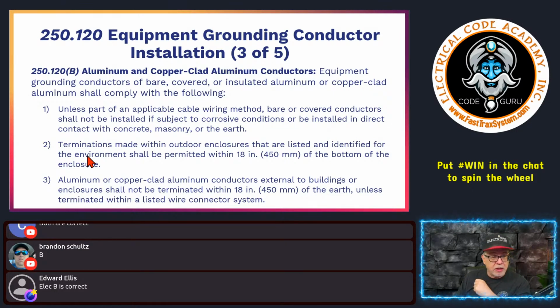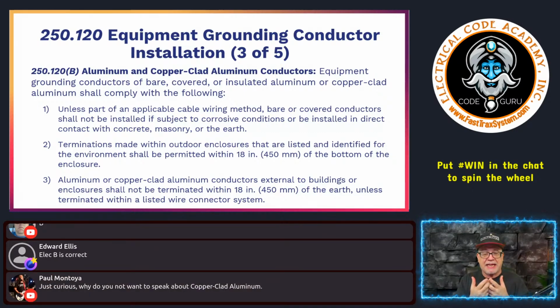Number two, terminations made within outdoor enclosures that are listed and identified for the environment shall be permitted within 18 inches of the bottom of the enclosure. So that's saying if you're bringing in wiring methods that have aluminum or that other type of conductive material other than copper, you can make these terminations within 18 inches of the earth as long as the enclosure that you're terminating in is rated for the environment. That'd be like a NEMA 3R and things like that.